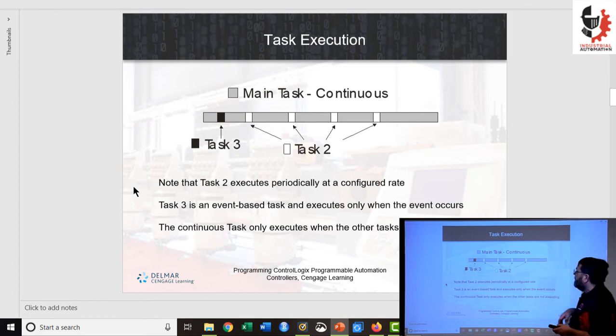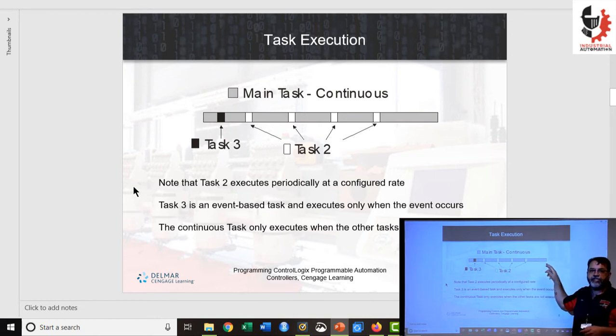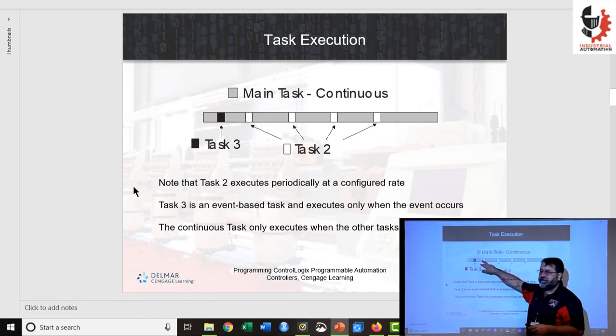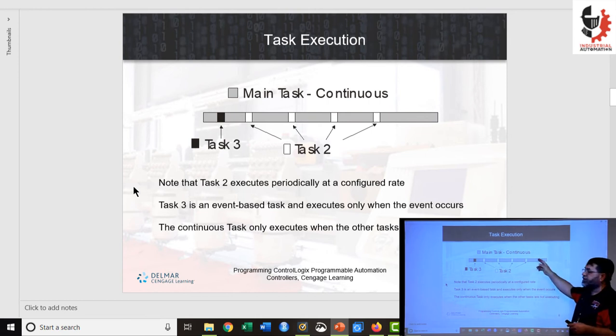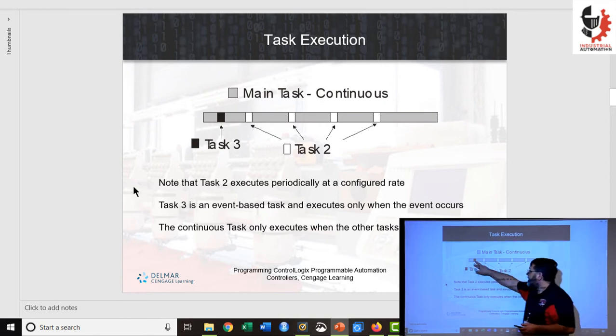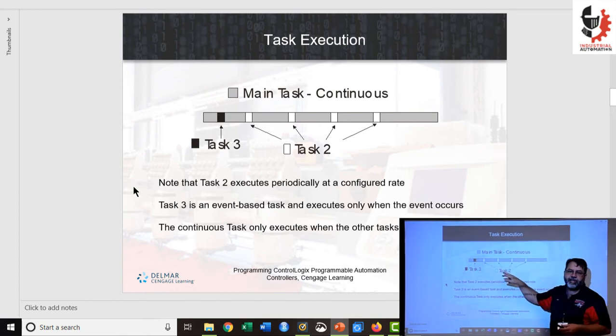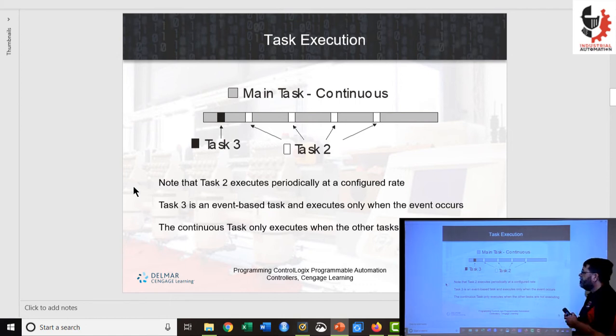Here they are shown graphically. We have the main continuous task — it's always running and has the lowest priority. It can be interrupted by a periodic task, which happens on a regular basis: it interrupts the continuous task, does its work, and then the continuous task resumes. We can also have event tasks, and both event tasks and periodic tasks can have different priorities, so you can configure which has the greatest priority.